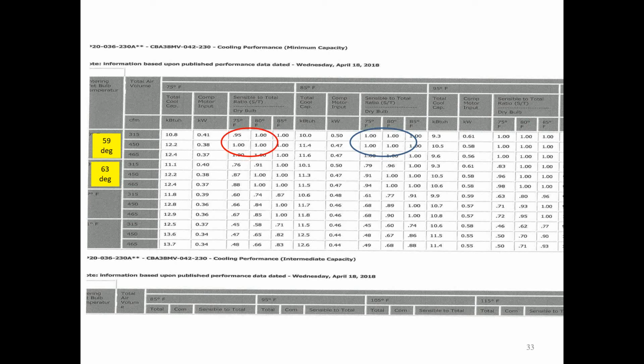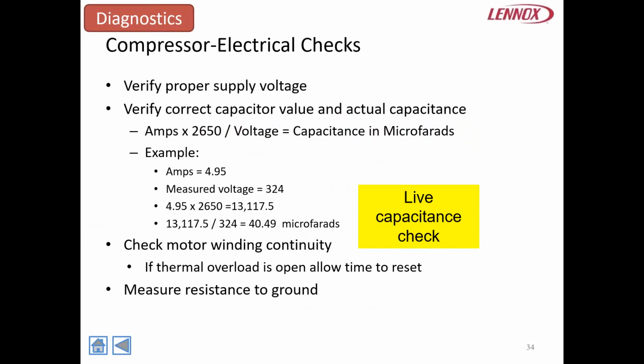At 95 degrees outside, I do understand it does get a little hotter than 95 outside, and you do have customers that want it at 72 and not the normal 75 that everybody kind of talks about. So you have to obviously evaluate your customer when you're talking to them to see what they like. If a customer likes it 68 degrees inside, then that's a different situation as well, and you have to allow for that. But just understand that as we crank this system up and it's at lower capacity, it's not designed to remove humidity, because essentially when it's cooler outside, there's not any humidity out there. We don't have humidity concerns yet, right? And so we have capacity concerns, and we can run down. So it's very important. I hope this opens your eyes a little bit about what you may see here.